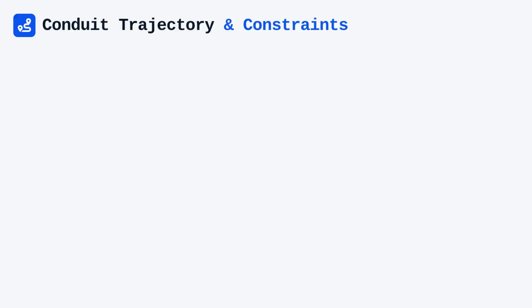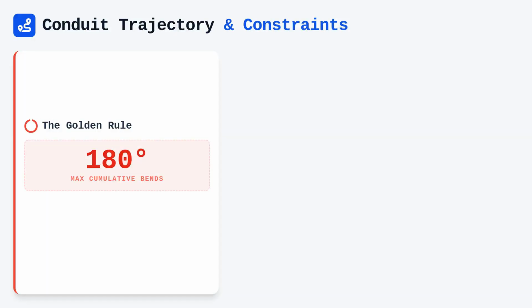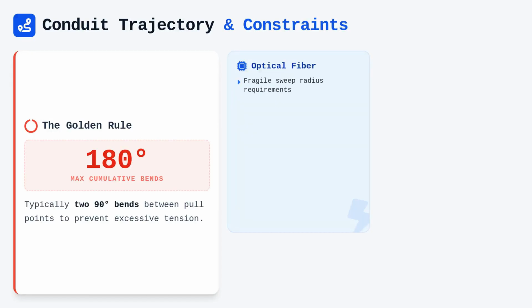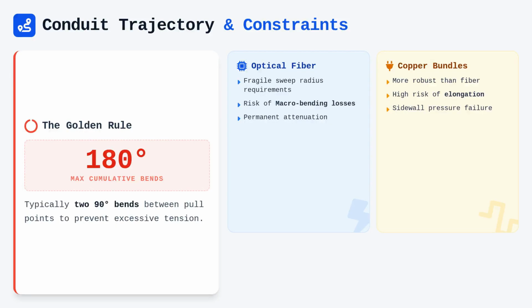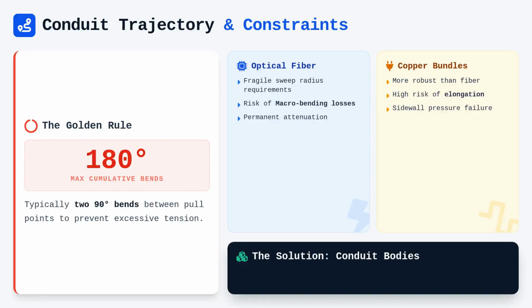Managing the trajectory of a conduit run requires strict adherence to geometric constraints. The standard limitation is a maximum of 180 degrees of cumulative bends between pull points, which usually translates to 2 90-degree bends or equivalent sweeps. If your pathway exceeds this, you are significantly increasing the pulling tension and the risk of sidewall pressure exceeding the cable's rating. For optical fiber, the sweep radius is particularly critical because fiber is fragile. Sharp bends can result in macro bending losses and permanent attenuation. Copper bundles, while more robust, are prone to elongation if they are forced around too many obstacles. Therefore, the implementation of conduit bodies like LBs, LLs, and LRs is not just about getting around a corner. These fittings facilitate easier cable transition, provided the internal dimensions of the body are designed to accommodate the bend radius of the specific media being installed.